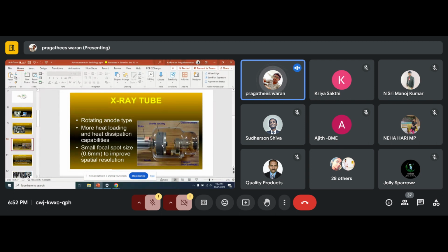As you are all aware, only 1%. We supply 1,20,000 volts to the tube, and out of this, only 1% is converted into X-ray. Everything else is converted into heat, so we have to create very good heat dissipation. Only then will the lifetime of the tube increase. Heat dissipation units are mentioned as MHU, mega heat units.